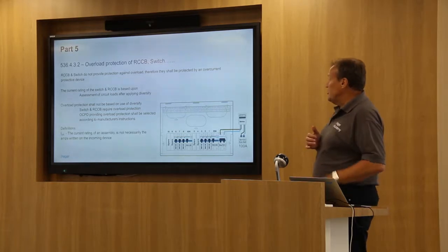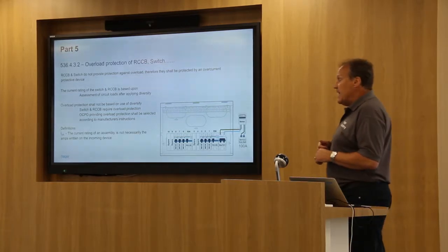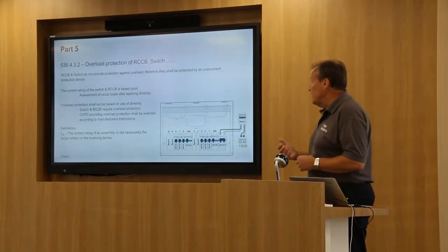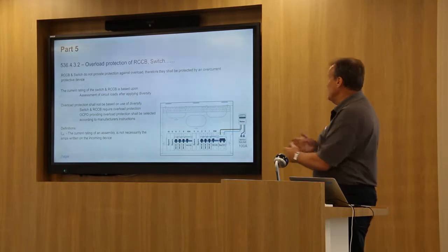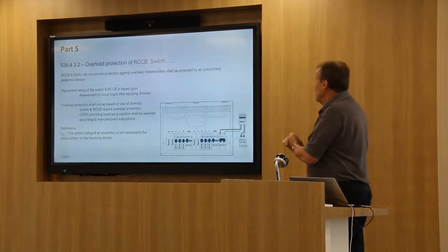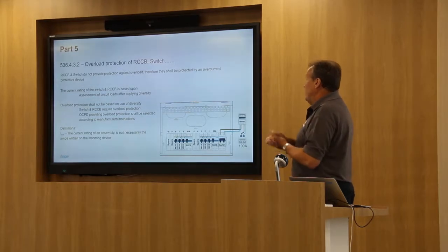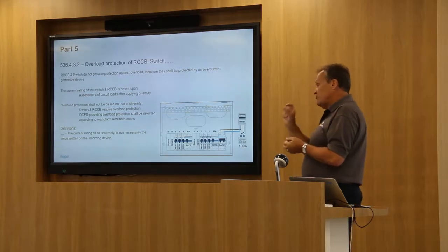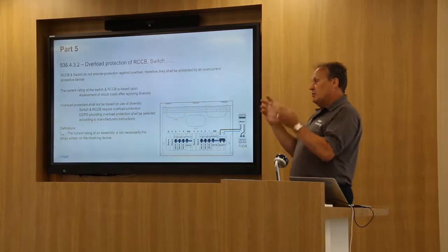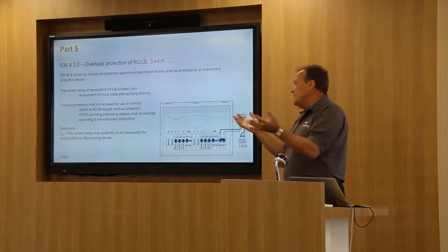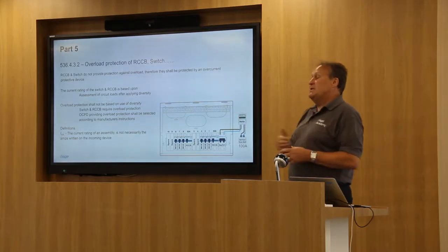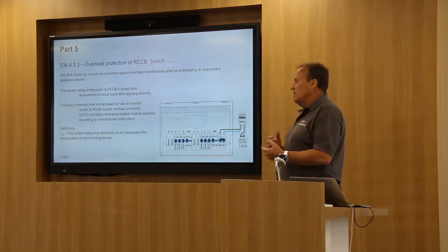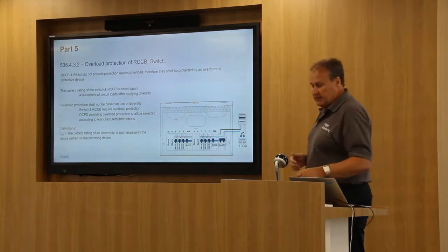Now, some terminology is introduced, some definitions which I need to cover. In is normally the symbol for current rating, which it is here, the current rating of the whole assembly. So this assembly is the consumer unit. And we can see here that it may or may not be the amps written on the incoming device. Just because that incoming main switch there might have 100 amps written on it, okay, the manufacturer of this assembly, i.e. the box with all the bits in it, has to state whether this assembly is suitable for 100 amps, and it will usually be on their literature, their labelling, or something like that with the product.